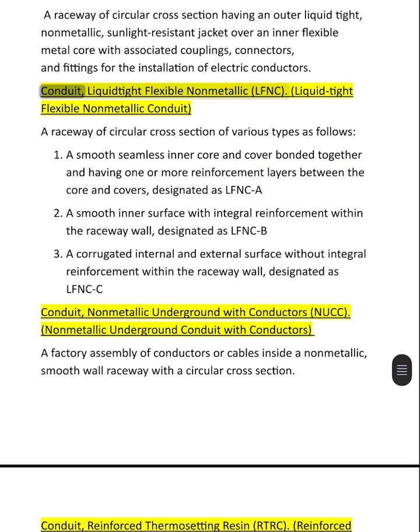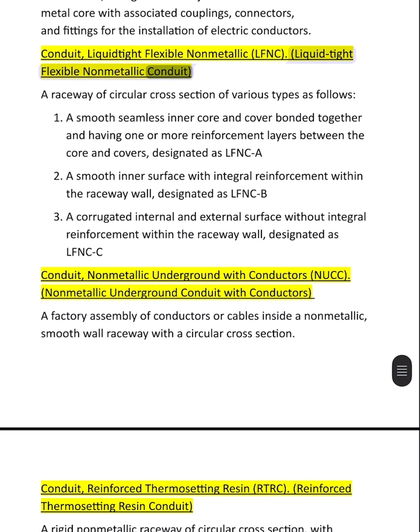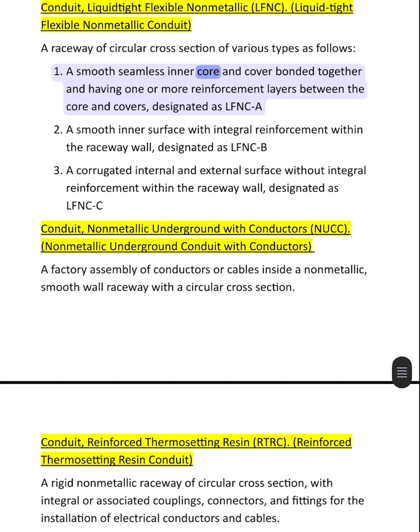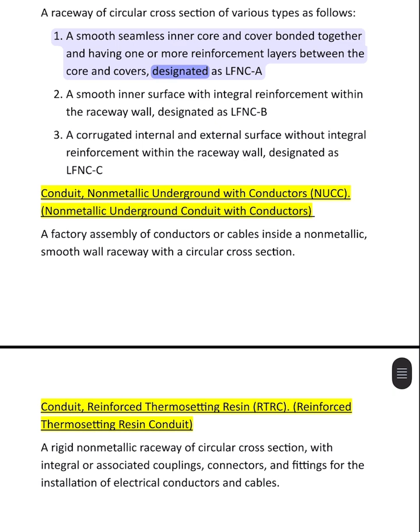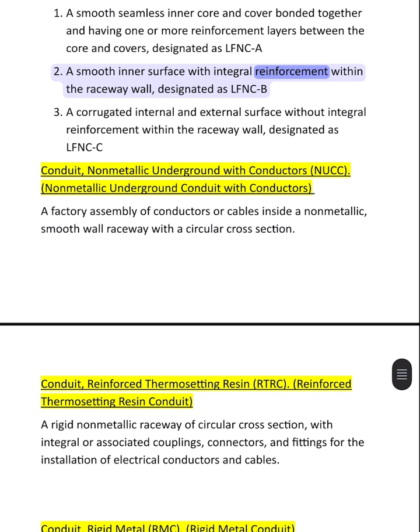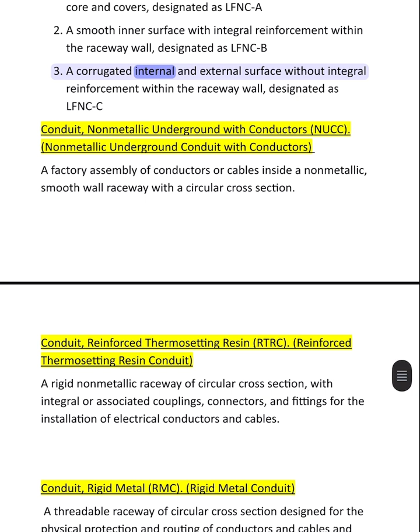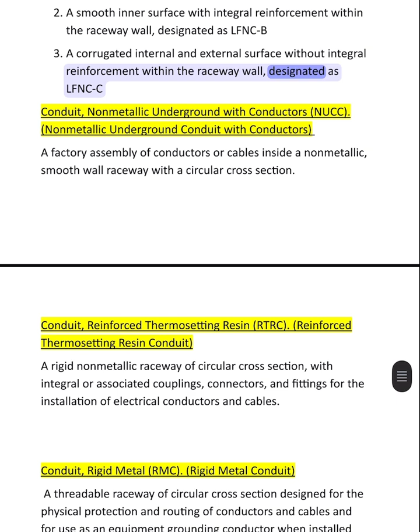Conduit, liquidtight flexible non-metallic, LFNC: liquidtight flexible non-metallic conduit, a raceway of circular cross-section of various types as follows. 1. A smooth seamless inner core and cover bonded together and having one or more reinforcement layers between the core and covers, designated as LFNC-A. 2. A smooth inner surface with integral reinforcement within the raceway wall, designated as LFNC-B. 3. A corrugated internal and external surface without integral reinforcement within the raceway wall, designated as LFNC-C.